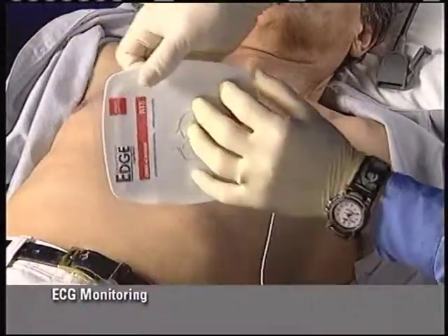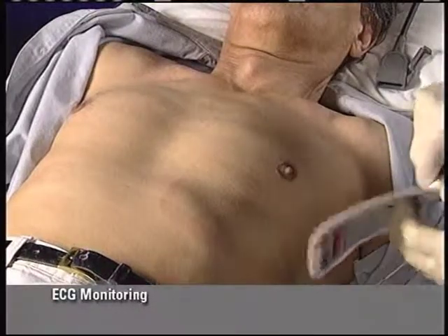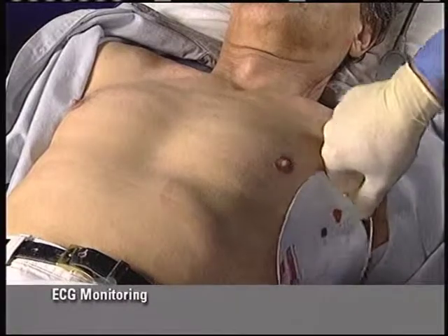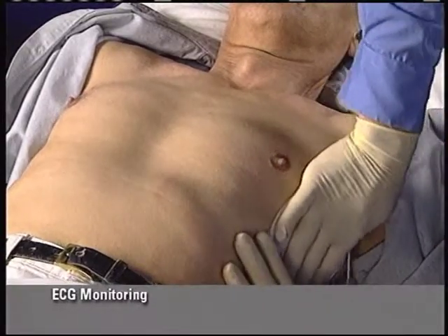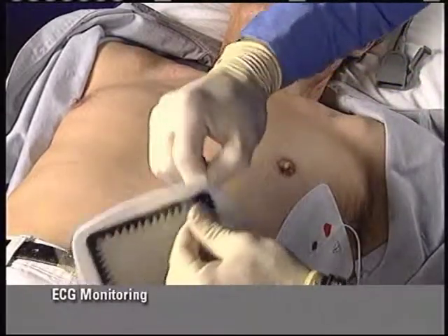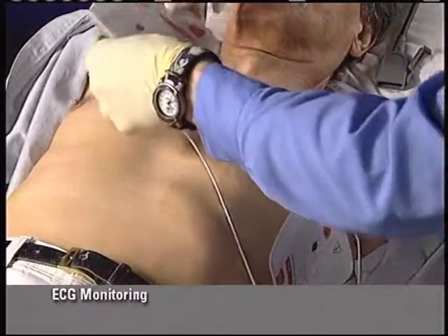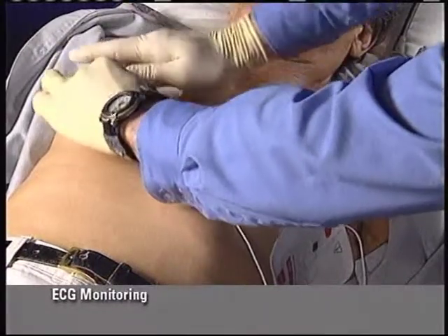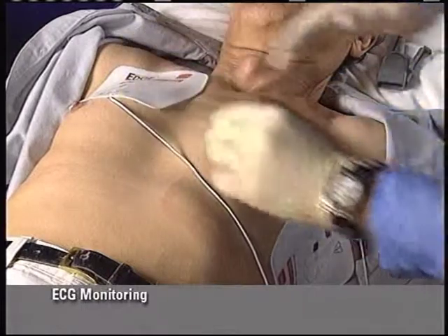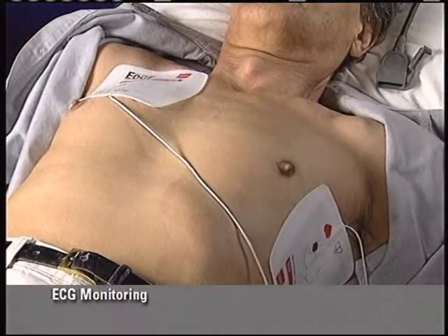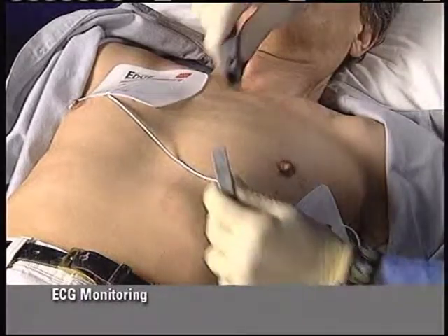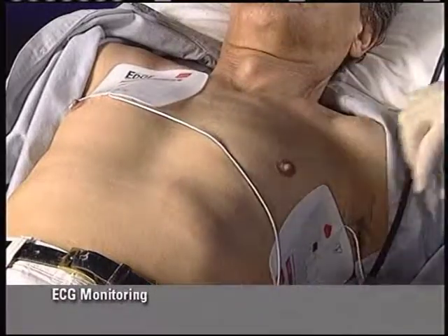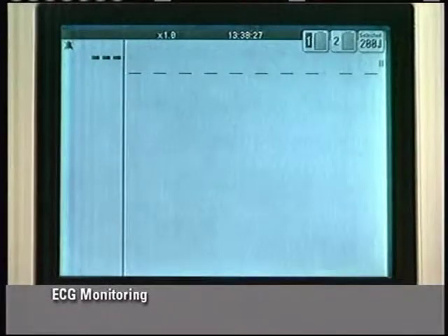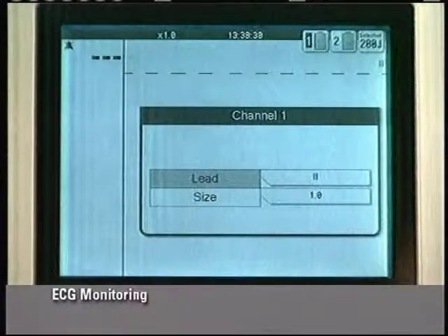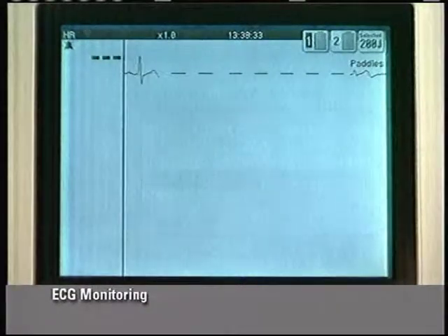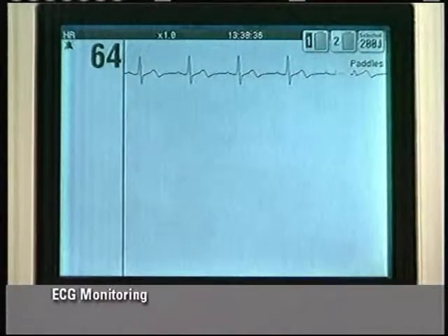After removing the backing from the electrode, apply the electrodes on the patient's chest in the anterior lateral position. The electrode with heart symbol is placed lateral to the patient's left nipple in the mid-axillary line. The other electrode is placed to the right of the sternum below the clavicle. Press the electrodes firmly from one end to another to prevent entrapment of air. Connect the electrodes to the therapy cable. Check that the ECG is displayed on the screen. If the power on default for the ECG is lead 2, select paddles lead. As previously described, check the ECG size and that heart rate counting is correct.